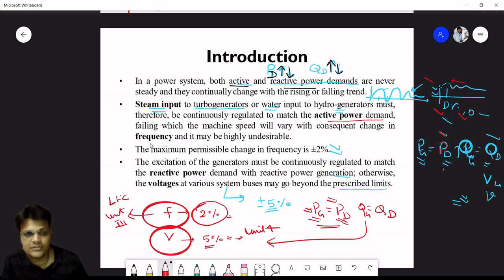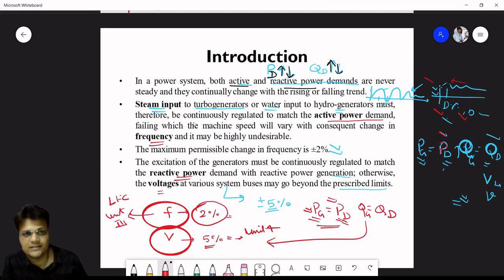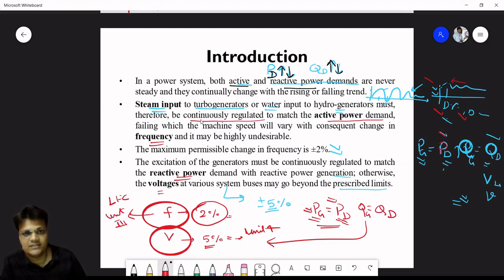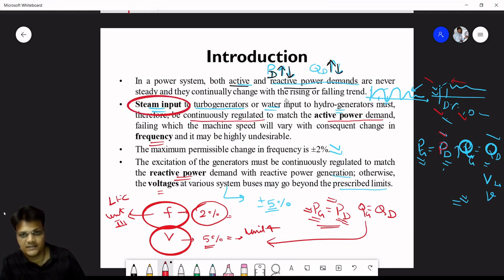Active power demand is related to frequency; reactive power demand is related to voltage. Steam input to the turbo-generator, or water input to the hydro-generator, must therefore be continuously regulated — increased or decreased — to match the active power demand.